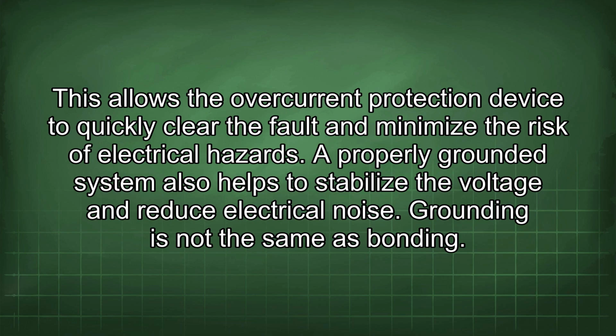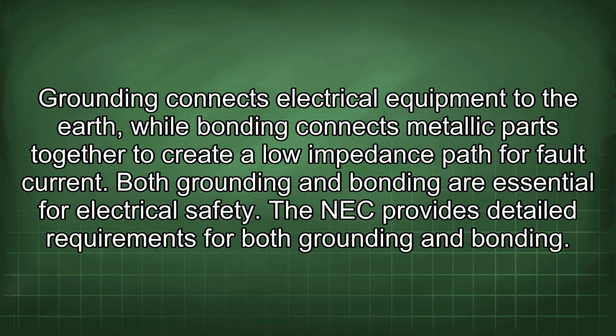Grounding is not the same as bonding. Grounding connects electrical equipment to the earth, while bonding connects metallic parts together to create a low impedance path for fault current. Both grounding and bonding are essential for electrical safety. The NEC provides detailed requirements for both grounding and bonding.